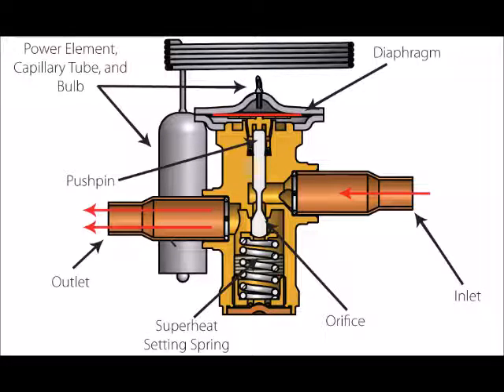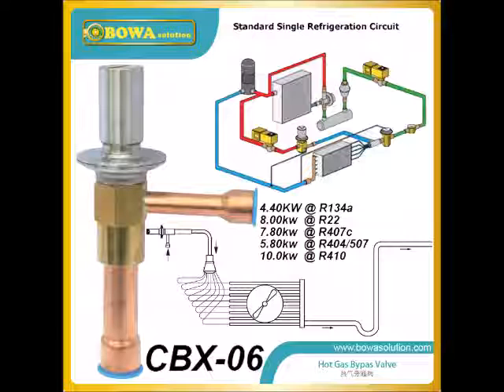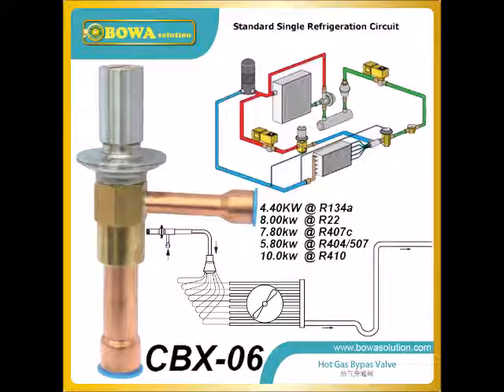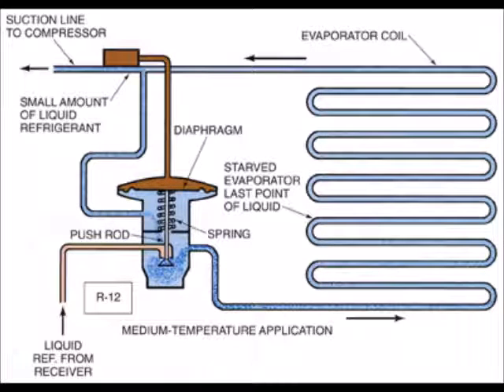An increase of flow rate lowers the temperature of the evaporator and allows for more heat absorption. Types: There are two main types of thermal expansion valves — internally or externally equalized. The difference is how the evaporator pressure affects the position of the needle. In internally equalized valves, the evaporator pressure against the diaphragm is the pressure at the inlet of the evaporator, whereas in externally equalized valves, it is the pressure at the outlet. Externally equalized thermostatic expansion valves compensate for any pressure drop through the evaporator.